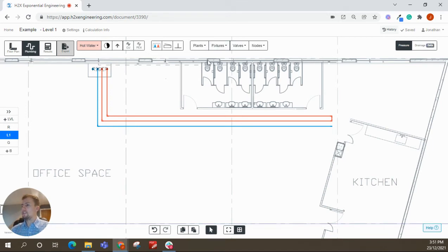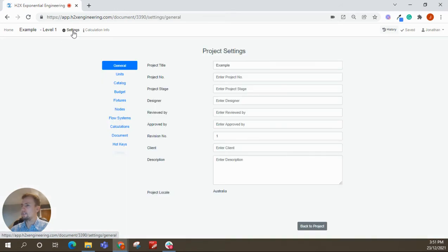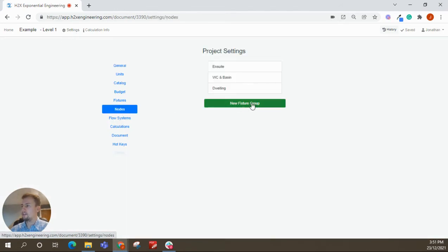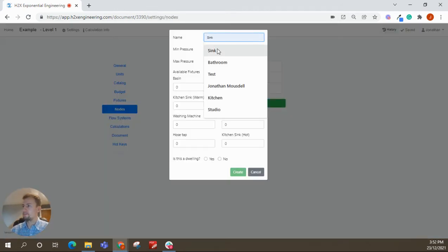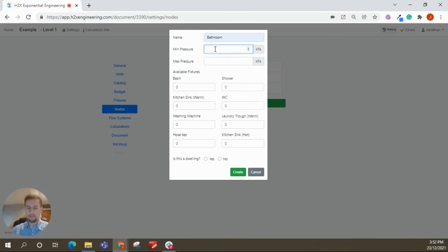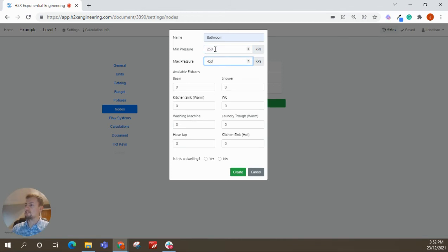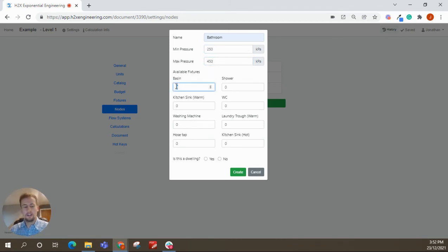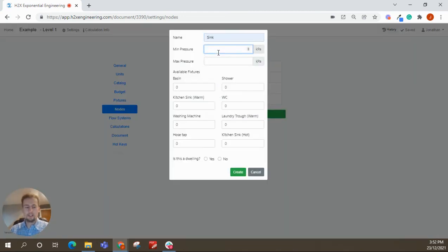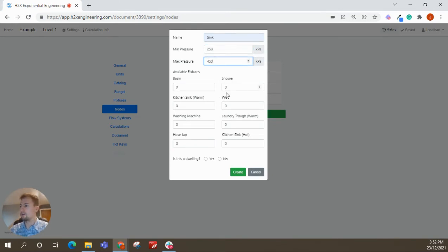All right. And in this area, this is where we're going to use nodes instead of fixtures. So for the nodes, we can go back to the settings that we saw before, and we just have to think what we want to make. So we'll create a new fixture group, call it bathroom. Done this before. Then just type in what the minimum pressure you want to achieve there is, and what the maximum is as well. And if you go outside that range, you'll see some warnings in the results. But it was three basins and four WCs. So we can create that one. And I'll also create one for that sink as well, which there it is. So sink, choose the pressures that I'm looking for. And create as many as you want.